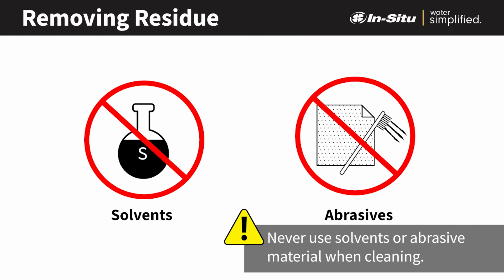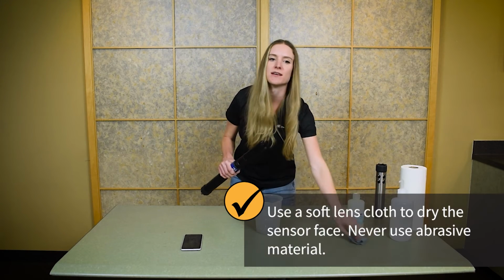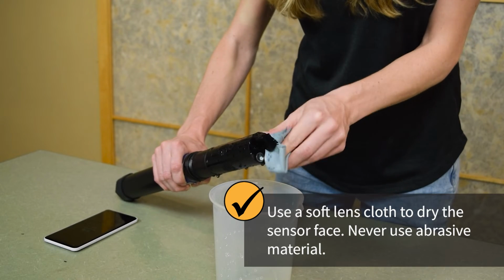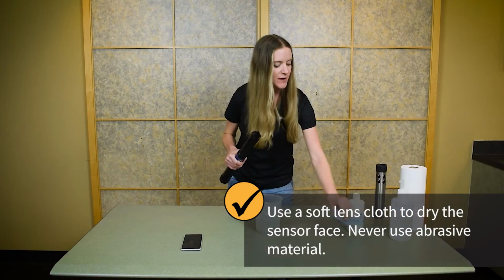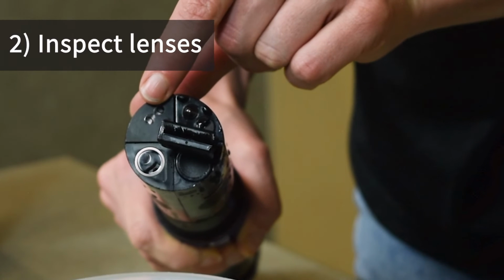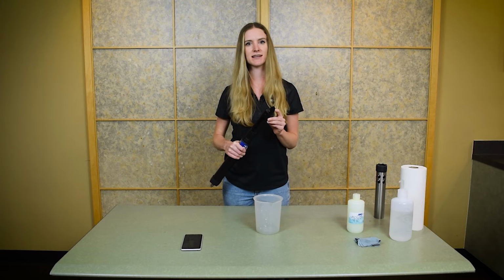Never use solvents, abrasives, or metal scraping tools on the sensor. If you remove the sensor for cleaning, reinstall it again in the instrument, and you can dry the sensor off with a soft cloth like a lens cloth. Inspect the lenses for any scratches. If you notice any major scratches and your sensor is not calibrating properly, you may need to replace the sensor.